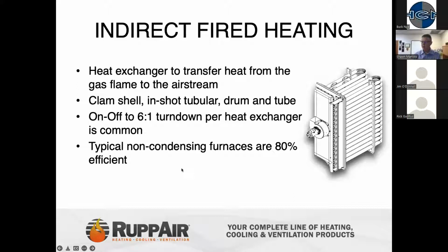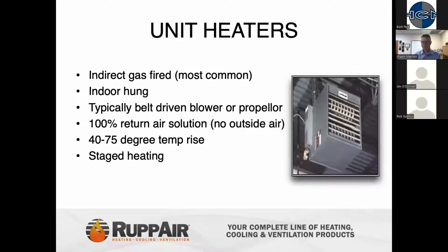Typically, non-condensing furnaces are about 80% efficient. Anytime you get above 80% efficient, you're going to start getting into a condensing type furnace. So the first category, and again, we're going to touch on basically three indirect fired common uses for heating these warehouses, is going to be unit heaters. The most common unit heater is going to be a gas fired. They do have electric and steam as well, but gas fired we're going to talk about today.